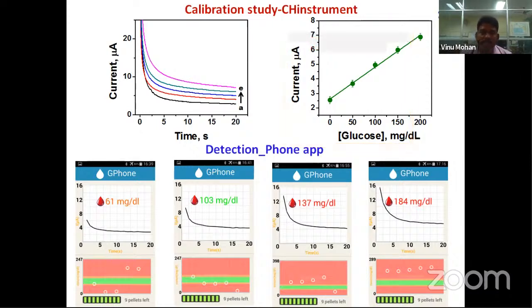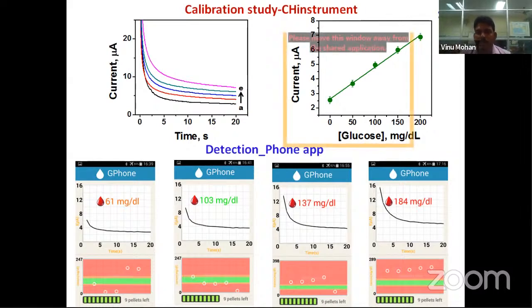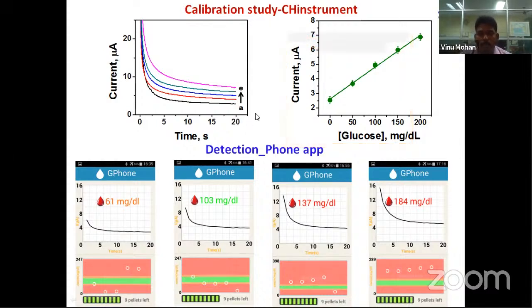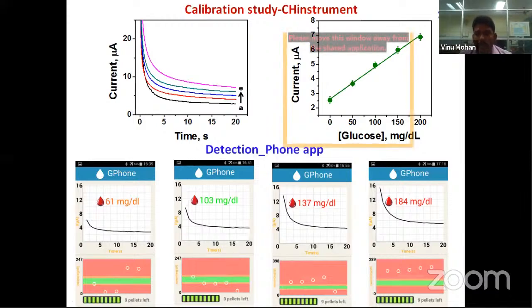The main challenge, of course, is that the sensor should be completely reproducible in nature. We have problems associated with functionalization of the sensing surface, because right now at the lab level we are functionalizing, like glucose or enzyme, whatever the surface functionalization, using our hand. So we definitely need an instrument for precisely monitoring and controlling the active layer in terms of volume or weight. Then the reproducibility or repeatability of the sensor won't be a problem, because in commercially available glucometers, they report an error percentage of sometimes 15 to 20%. That much error is already present in commercial glucometers themselves.